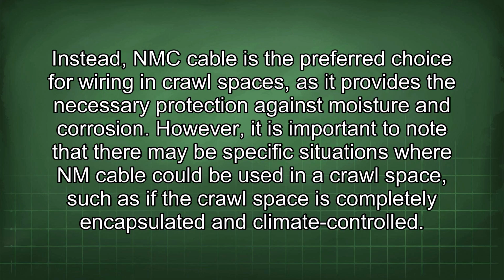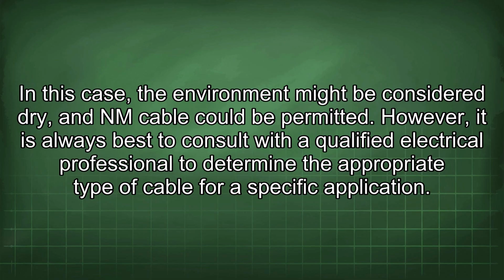and corrosion. However, it is important to note that there may be specific situations where NM cable could be used in a crawl space, such as if the crawl space is completely encapsulated and climate controlled. In this case, the environment might be considered dry and an NM cable could be permitted.